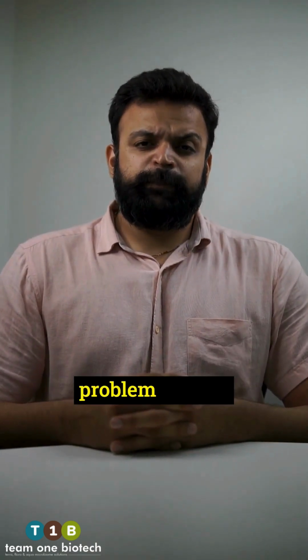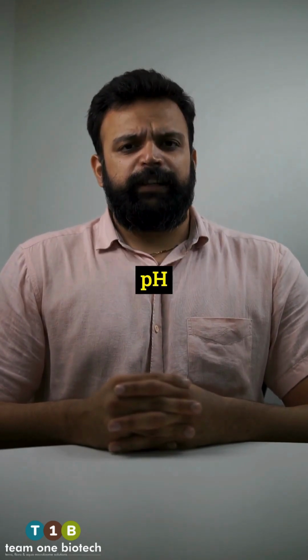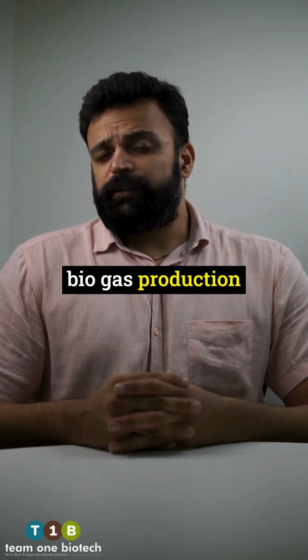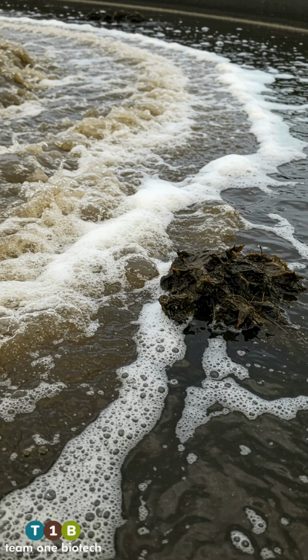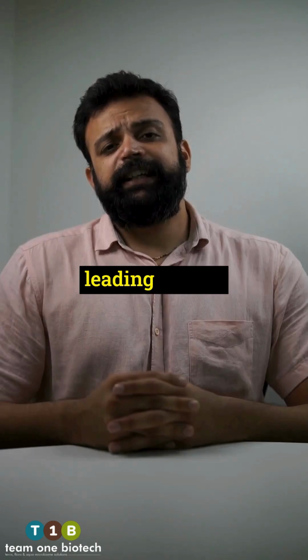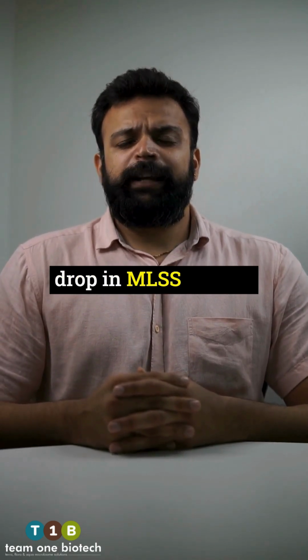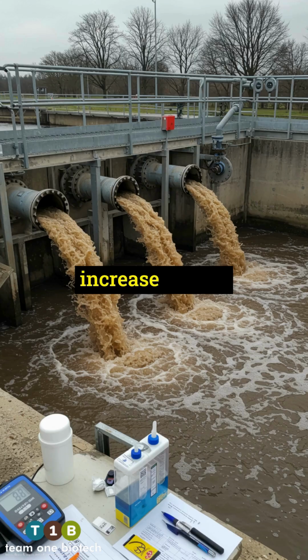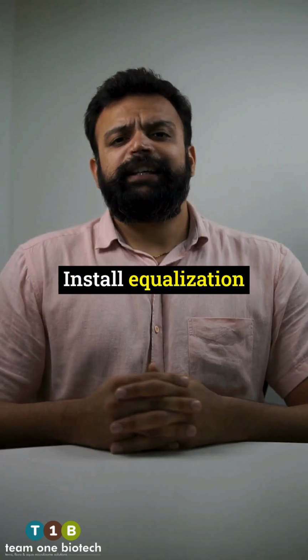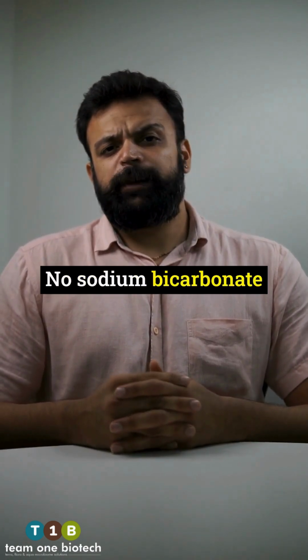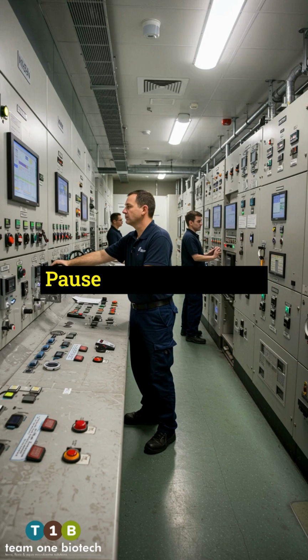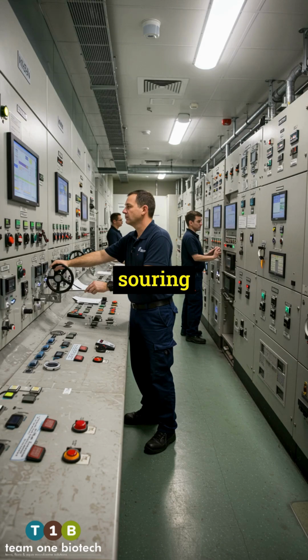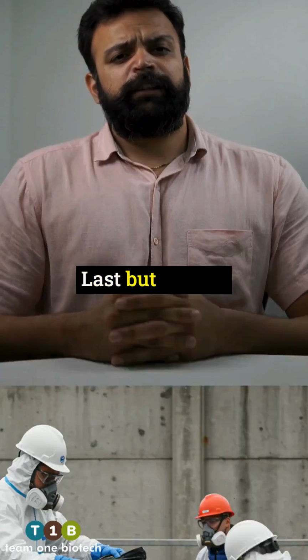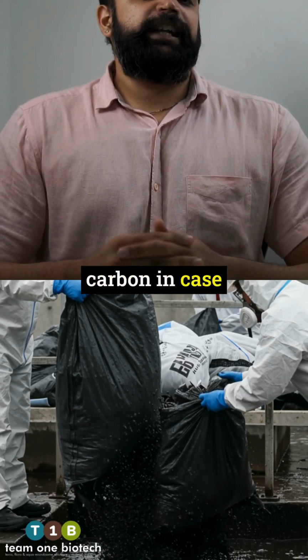The second persistent problem is toxic shock or pH crash. Symptoms: sudden drop in pH, rapid fall in biogas production, foaming or floating of sludge, accumulation of VFAs and sulfides, drop in MLSS and MLVSS levels, increase in BOD and COD levels at the outlet. How to fix it? Install an equalization tank upstream, dose sodium bicarbonate or lime for buffering, pause feed temporarily, and if the problem persists, reseed. Last but not the least, add activated carbon in case of emergency.